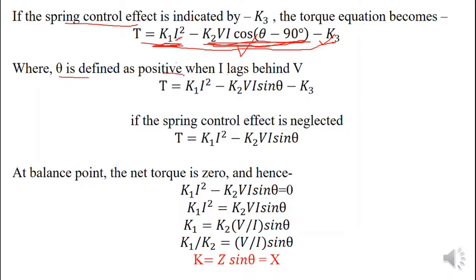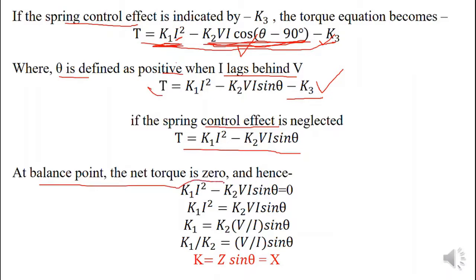Theta is defined as positive when I lags behind V. The torque equation is therefore modified to K1I² − K2VI sin θ − K3. Neglecting the spring control effect, the equation reduces to K1I² − K2VI sin θ. During the normal operating condition at the balance point, the two torques — operating and restraining — are equal. Modifying this equation, we get a constant K equal to Z sin θ, and since Z sin θ equals X, the reactance is equal to a constant during normal operating condition — essentially the preset value measured by the relay.